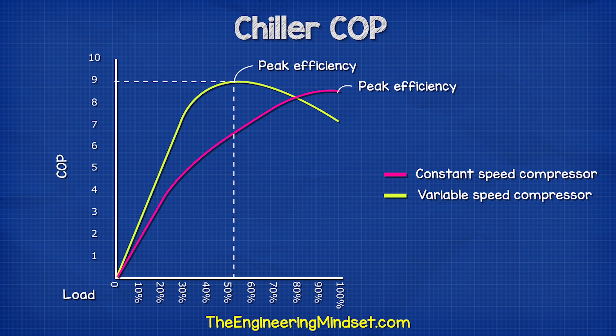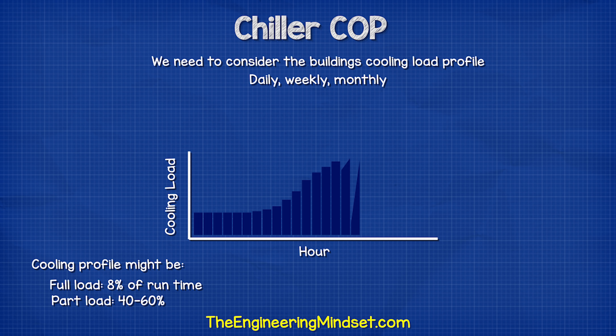In this example, we see that at around 50% load we get the highest COP of around 9. However, as the load increases in the peak of summer and we are approaching 90% load on the chiller, the COP becomes a lot lower at around 7, whereas the constant speed chiller will provide much more efficient and economical performance at this point. We need to consider the building's cooling load profile because typically it might only be at full load for perhaps 8% of the year and then spend 40% to 60% of the year at part load. So overall, the variable speed compressor would perform better, and in most scenarios this is true.